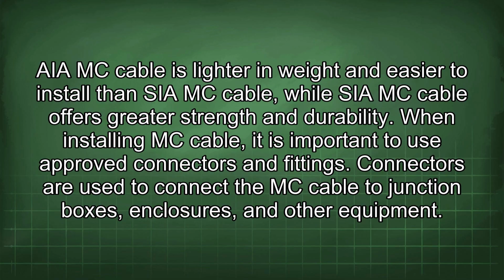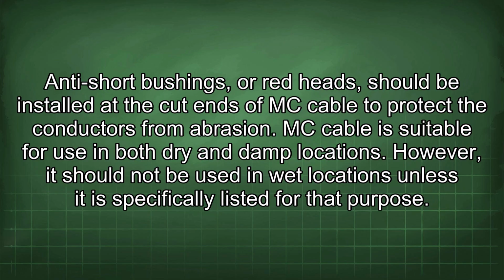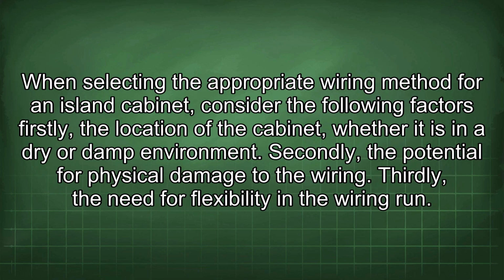When installing MC cable, it is important to use approved connectors and fittings. Connectors are used to connect the MC cable to junction boxes, enclosures, and other equipment. Anti-short bushings, or red heads, should be installed at the cut ends of MC cable to protect the conductors from abrasion. MC cable is suitable for use in both dry and damp locations. However, it should not be used in wet locations unless it is specifically listed for that purpose. When selecting the appropriate wiring method for an island cabinet, consider the following factors. Firstly, the location of the cabinet, whether it is in a dry or damp environment.